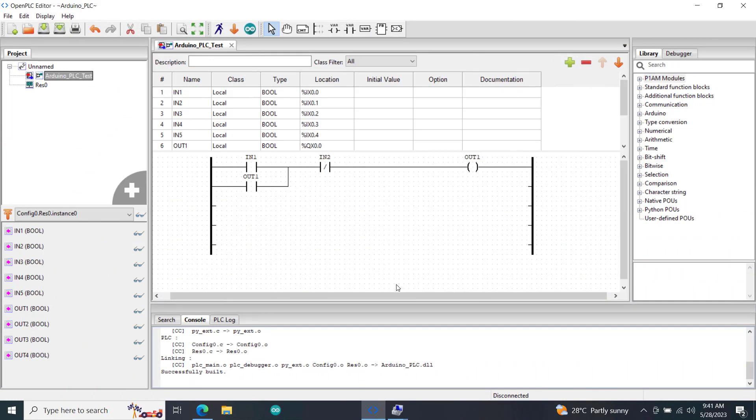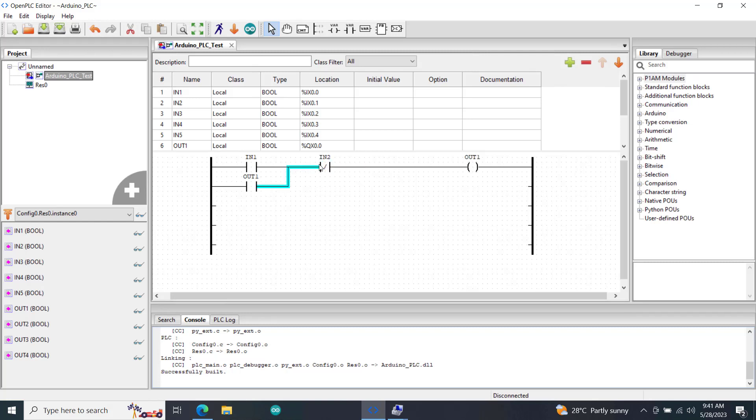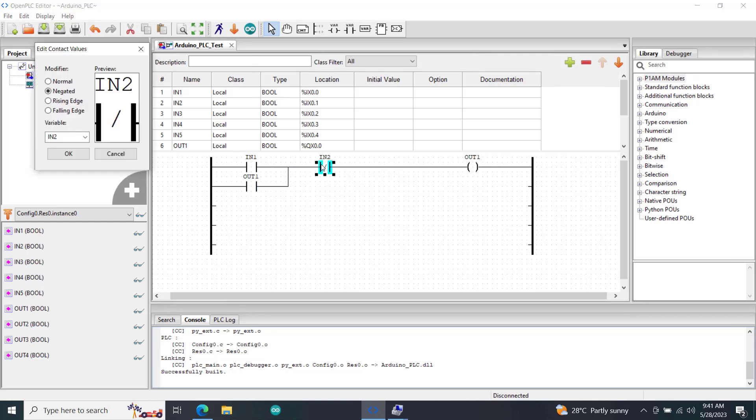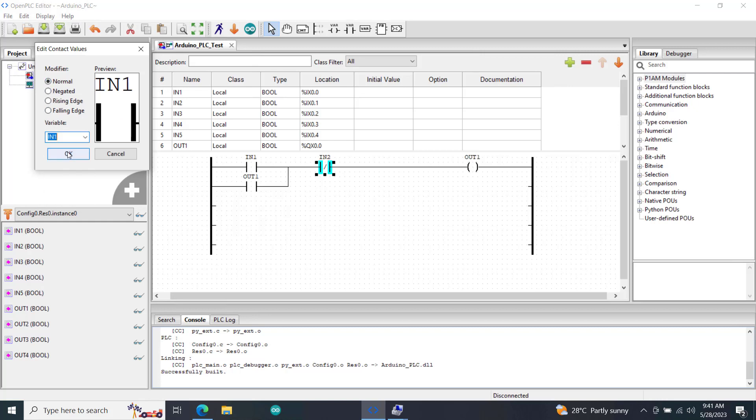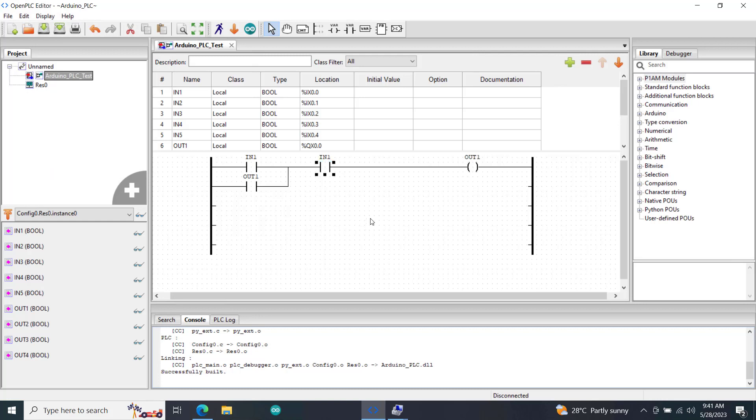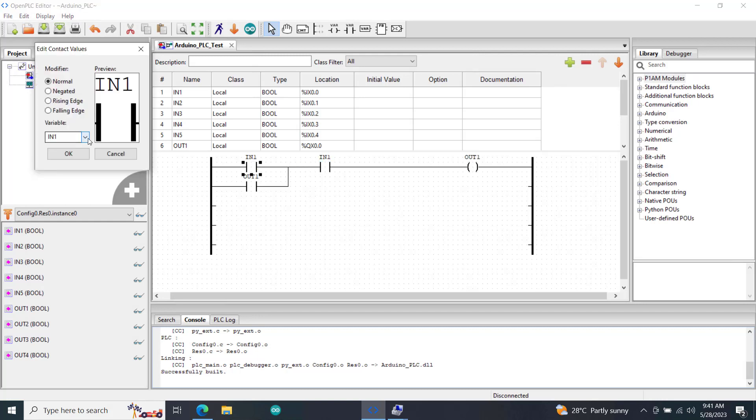To make it safe we need to rewire the circuit and make our logic normally open and then make our wiring normally closed in the field, to create what we term as a fail-safe mode.